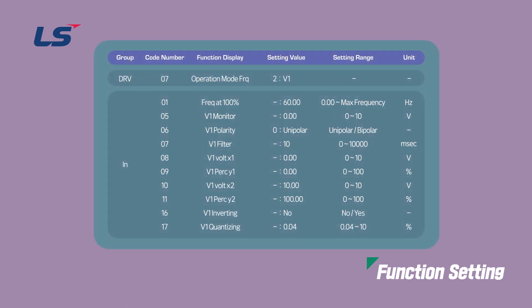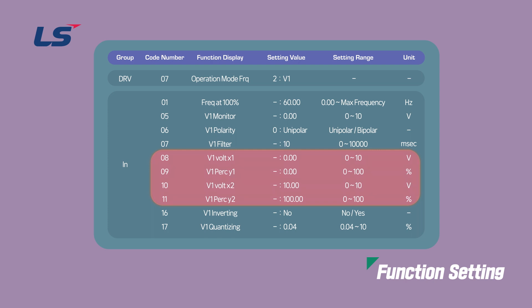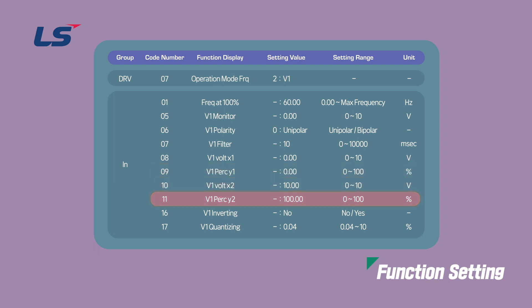Parameters related to analog input can be set in the IN group. IN group 6 does not use negative voltage, so set it to unipolar. If you want to use it from negative 10 volts to 10 volts, you can set bipolar. You can set the filter time constant for analog voltage input in IN group number 7. You can set the range of input voltage in IN group parameters 8 to 11, including minimum input voltage and corresponding frequency, and maximum input voltage.